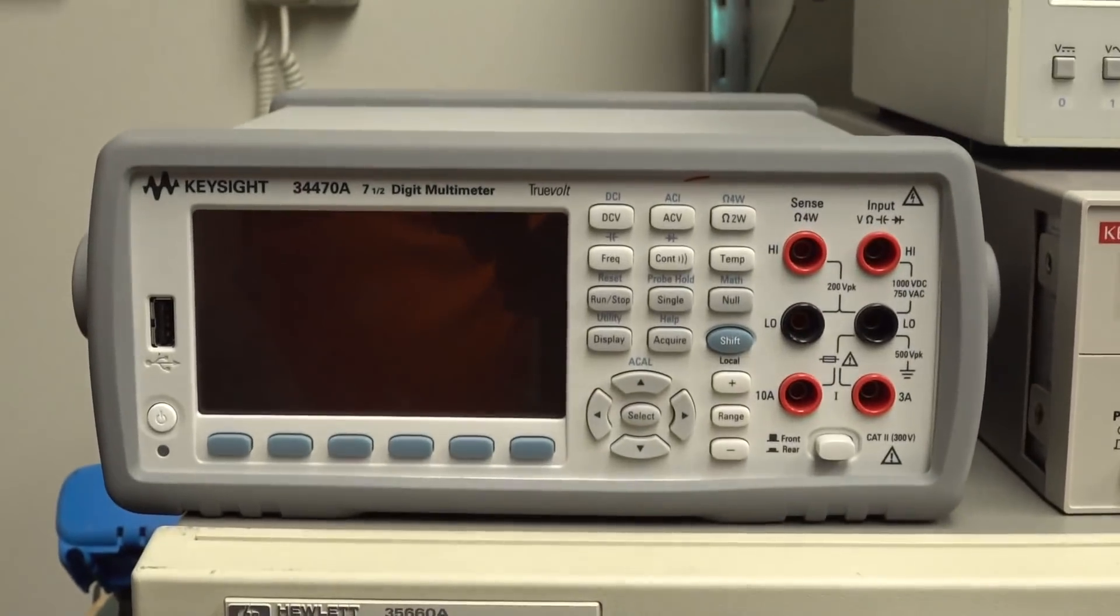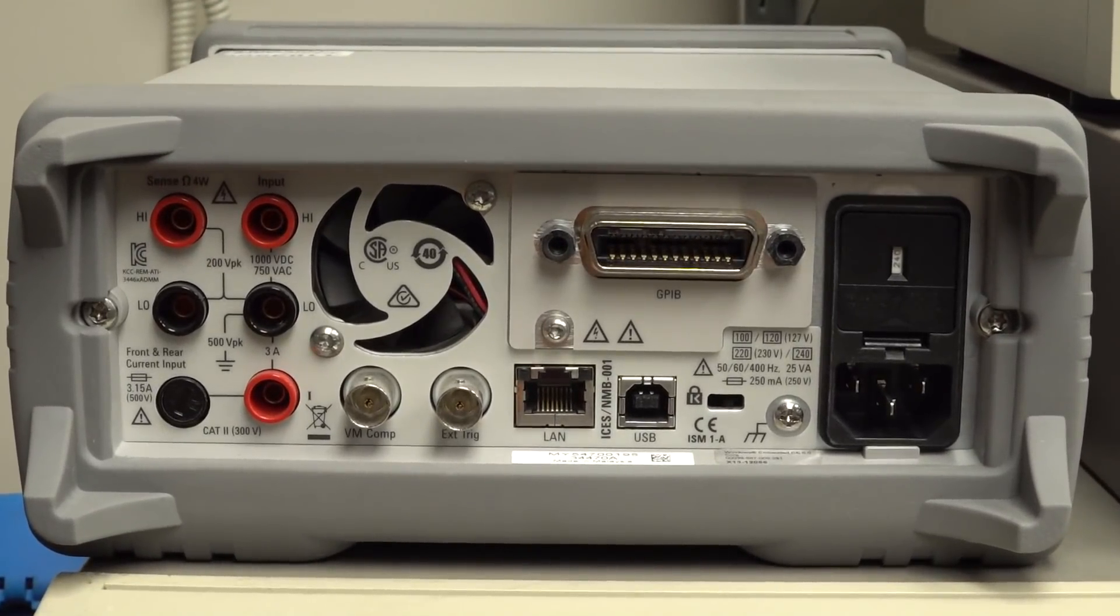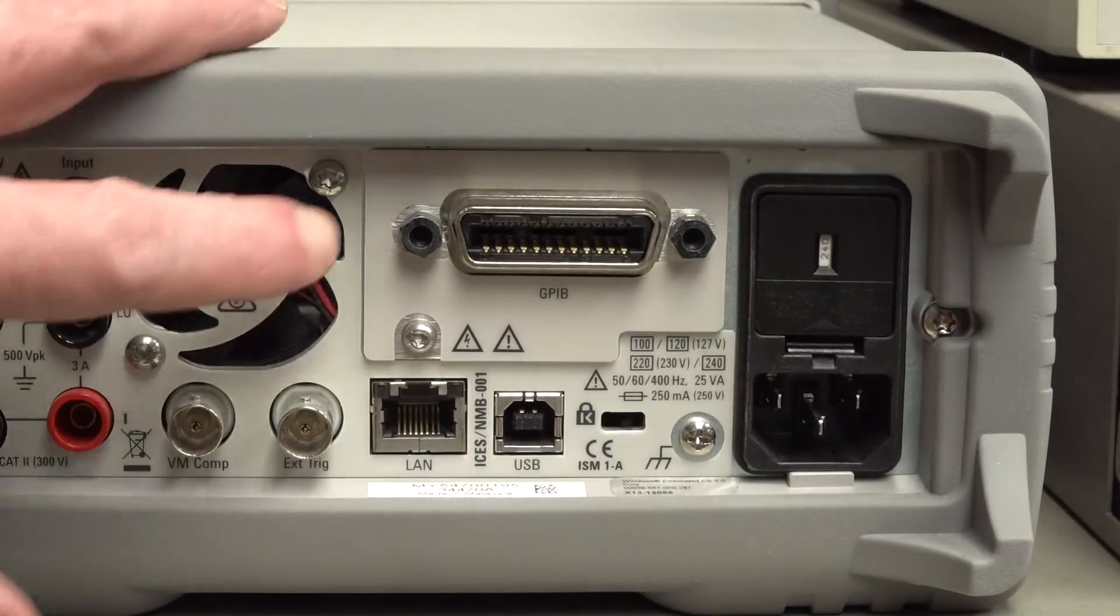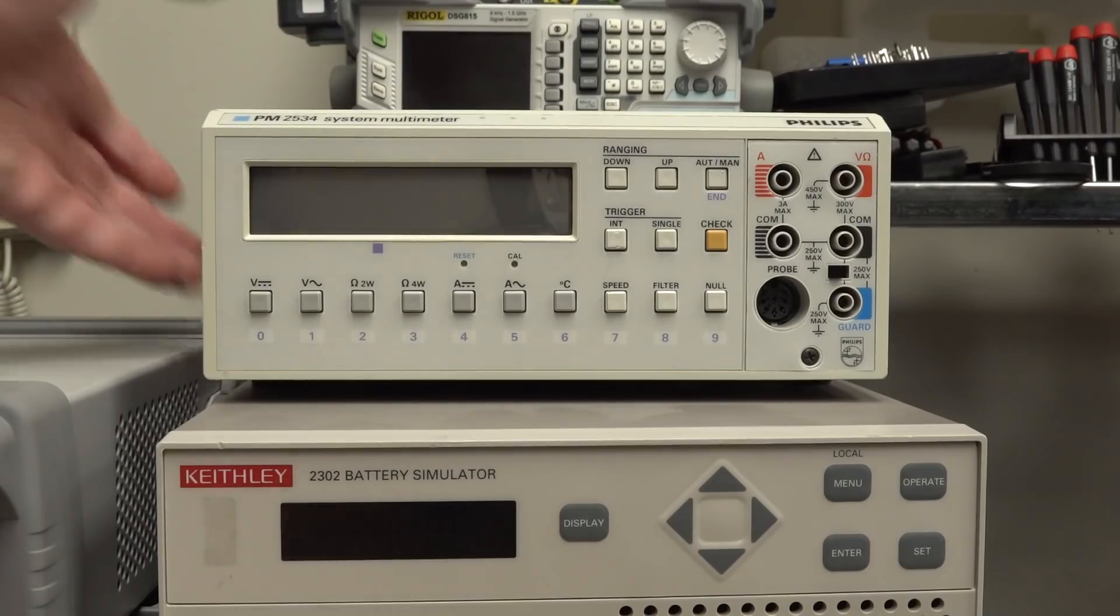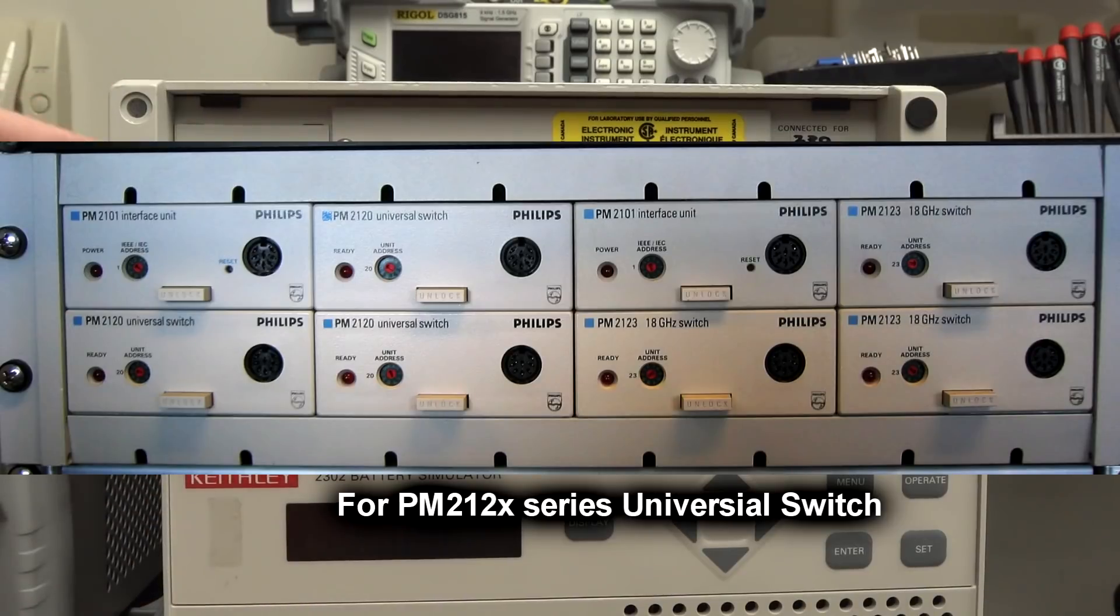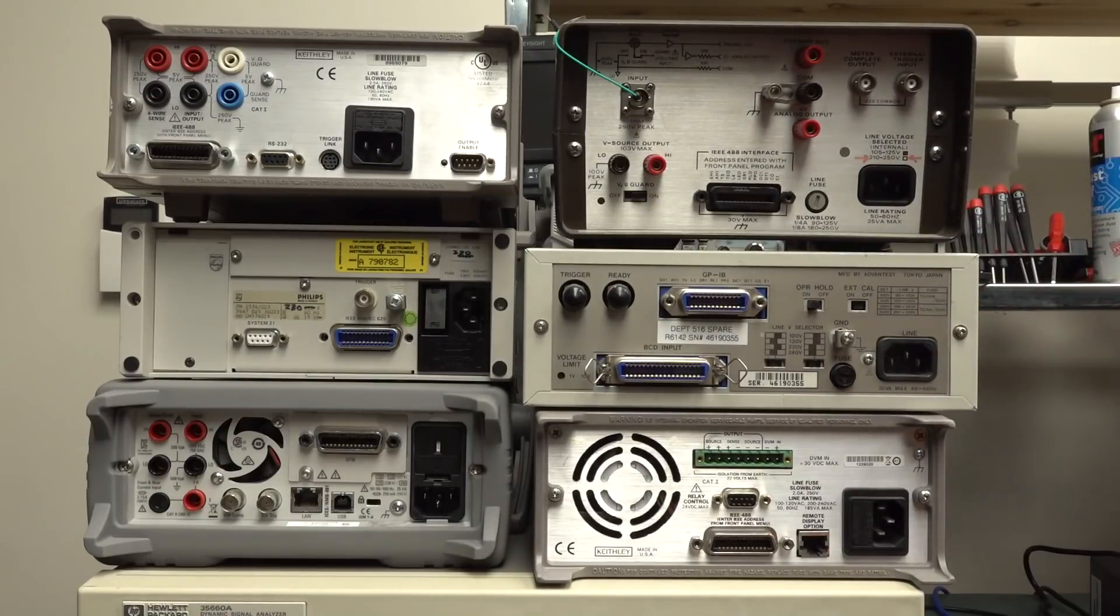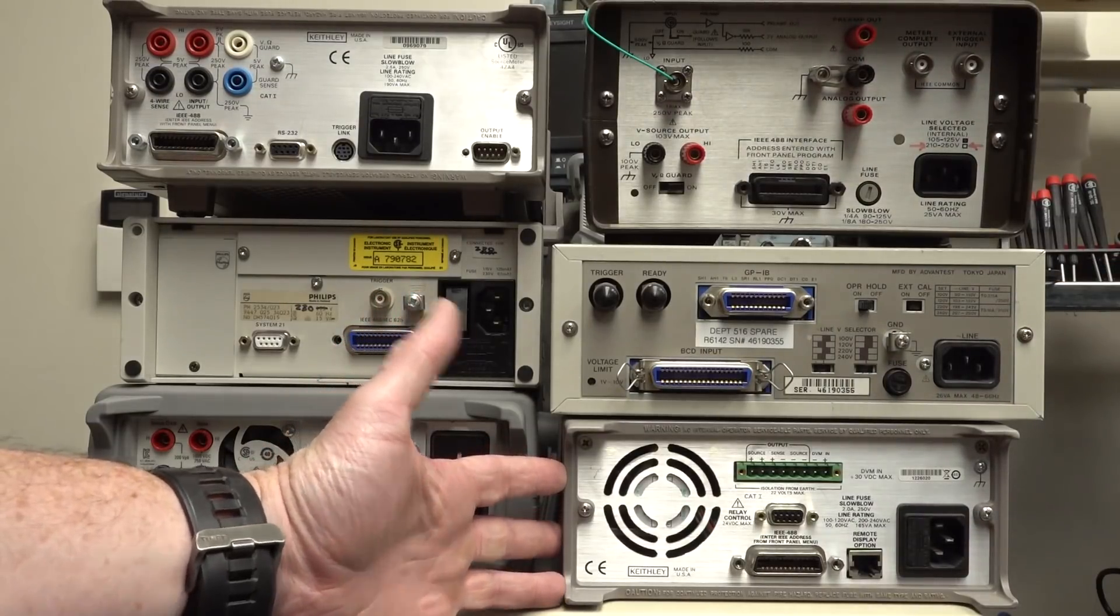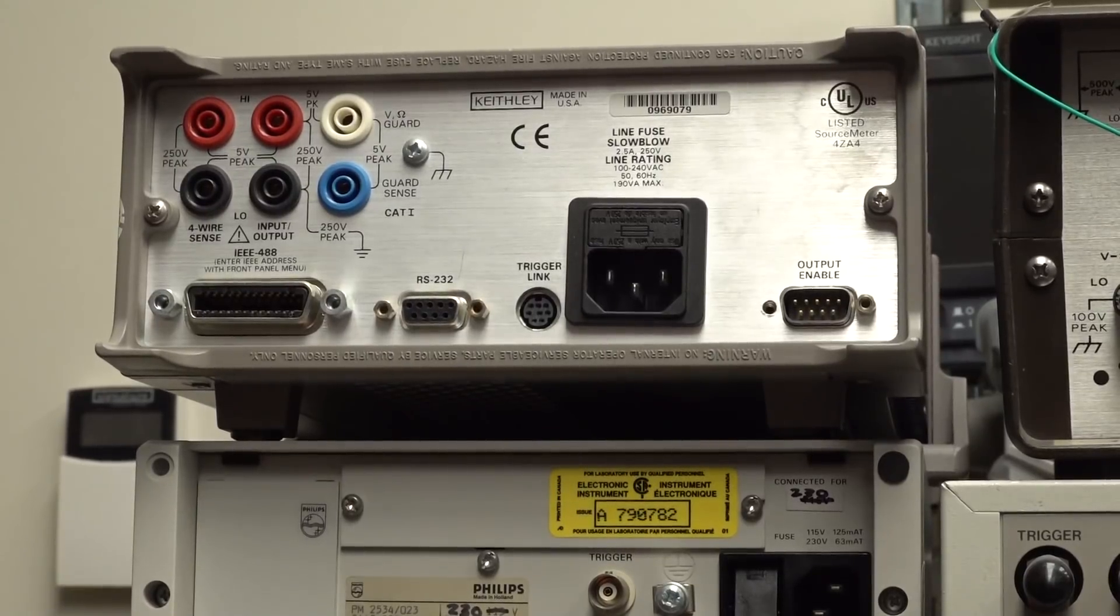Also known as GPIB, the General Purpose Interface Bus, or the IEEE 488 Standard. That's really the only way to talk to these instruments. It's been the de facto industry standard for a long time. You'll find racks and racks of gear even today all networked with GPIB. Even modern gear like this Keysight 7.5 digit meter is backward compatible.